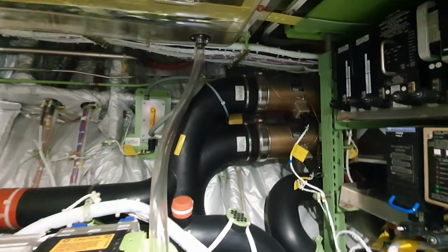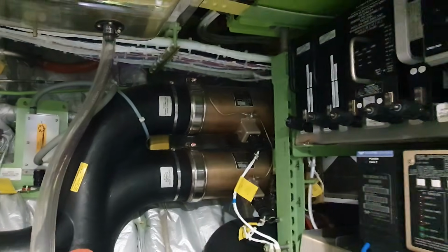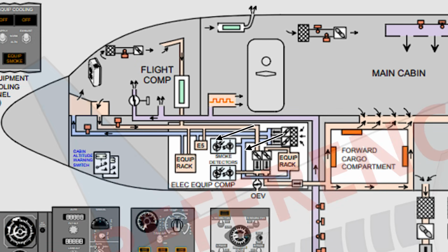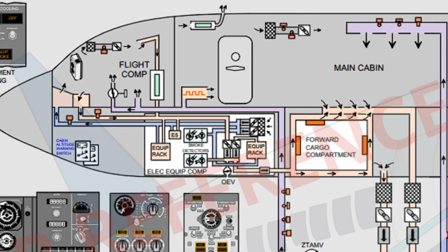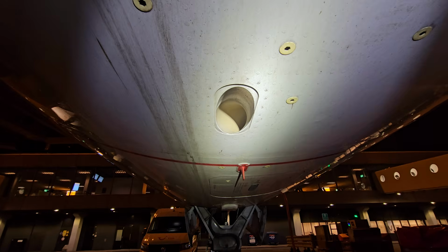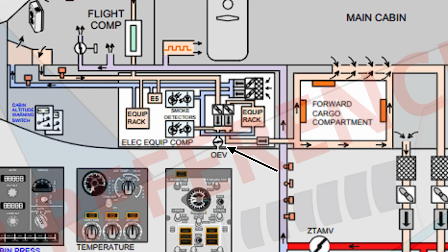We start with the supply fans, which draw air through a filter located in the equipment bay. This air is then directed to the equipment racks where the computers are housed and also to the computers in the flight deck. There are two supply fans in total. One serves as the primary unit and the other as an alternate. Only one fan per system operates at a time. The exhaust fans pull air from the equipment racks and the flight deck, then dump it overboard through the overboard exhaust vent. I'll tell you more about the overboard exhaust vent later.